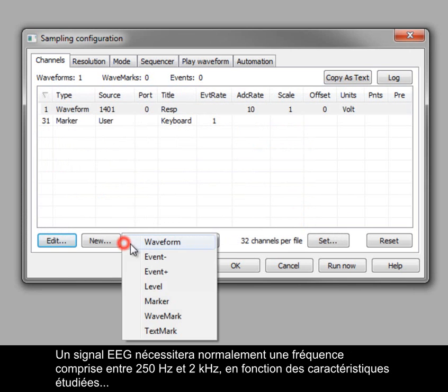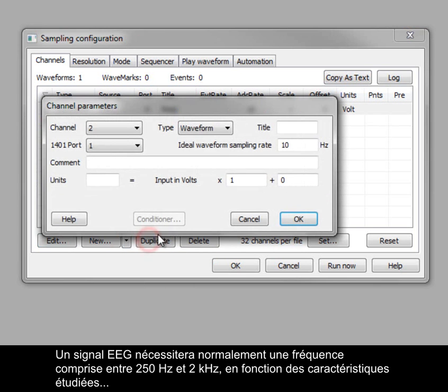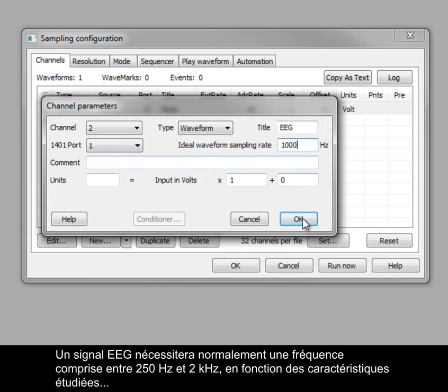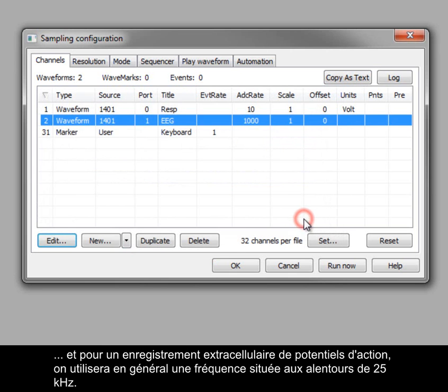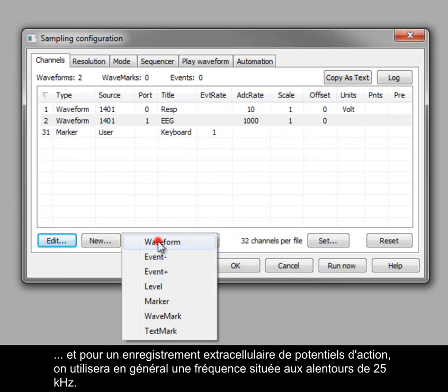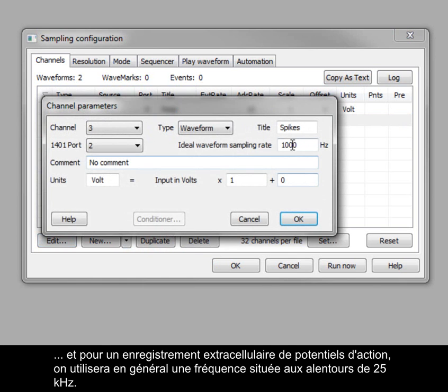An EEG signal would normally require between 250 hertz to 2 kilohertz, depending on the features of interest. And an extracellular recording of action potentials would usually require around 25 kilohertz.